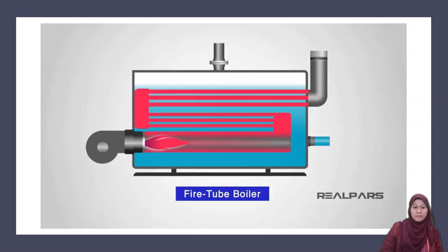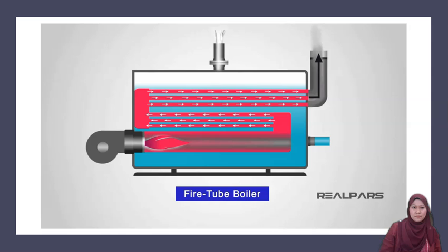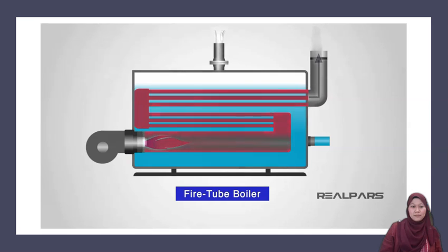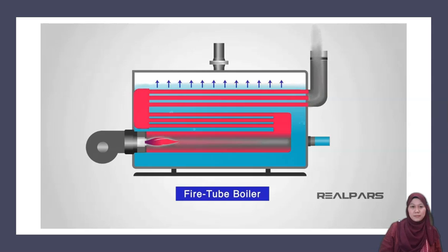Firstly, fire tube boilers. The typical makeup of this type of boiler is a furnace, a water tank acting as a boiler, and a smokestack. There are tubes running through the water tank carrying the heat from the furnace, and the smokestack vents the heat and gases caused by the heating effect so that the pressure does not continue to rise above the intended level. So, the fuel is burned inside the furnace. The tubes transfer the heat of the furnace through the water in the tank. Once it is heated, the steam generated is moved along downstream.